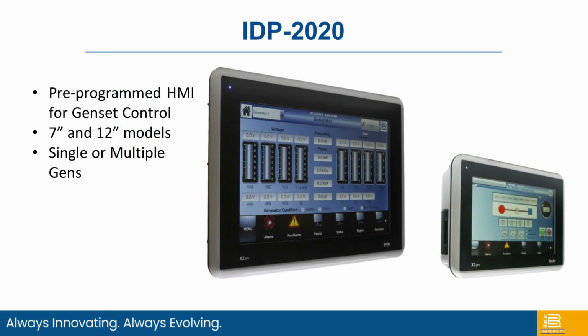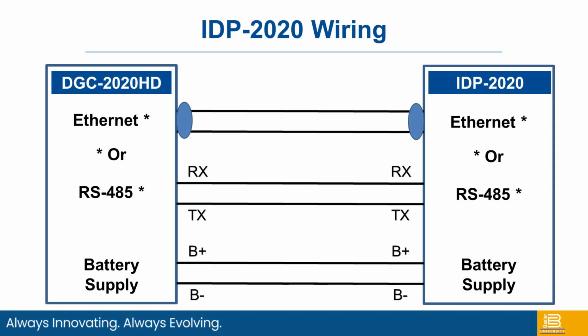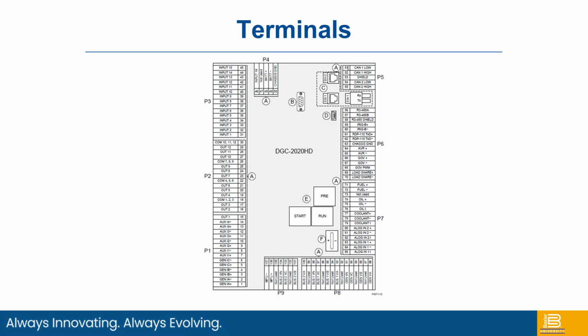We also have an IDP, which is an interactive display panel, with 7-inch and 12-inch color touchscreens, all pre-configured. So basically it's pretty much plug and play. You buy one, you install it, and it instantly communicates to the DGC-HD and starts displaying in its full function. So you can start, stop, read alarms, warnings, etc. This is done by Ethernet, so it's slightly different than the other accessory modules. If you do use an IDP, you'll need to make sure you have one of the Ethernet ports accessible, and also make sure that you have the style number with the Ethernet option and not the fiber optic option.